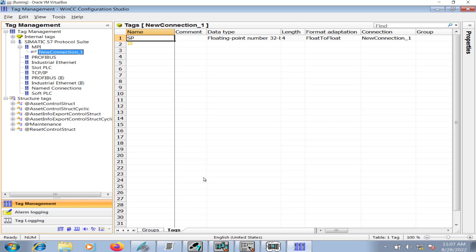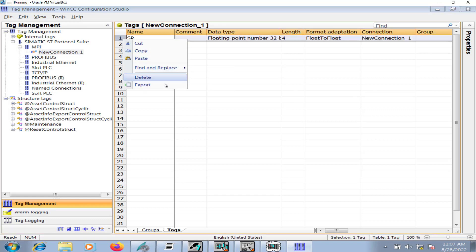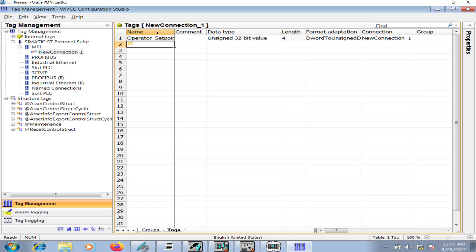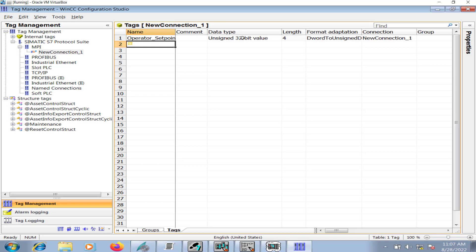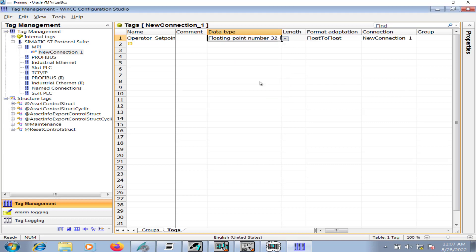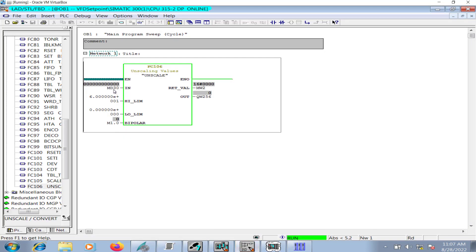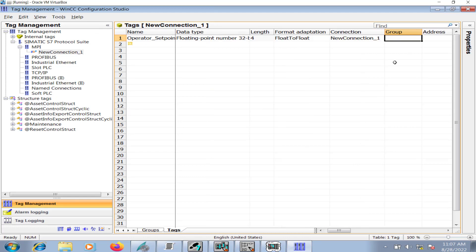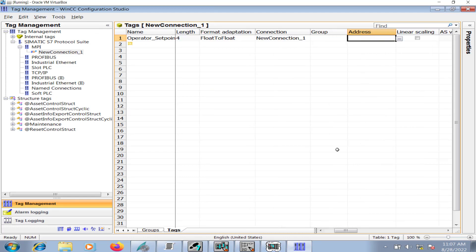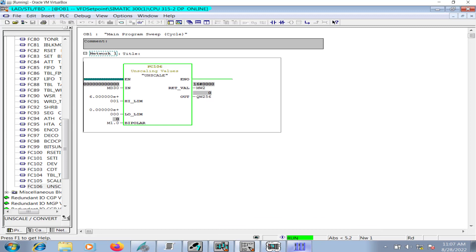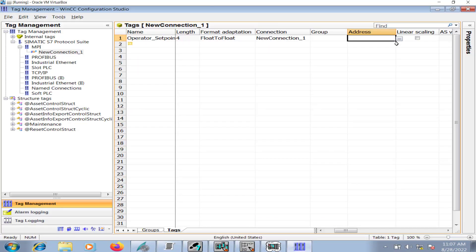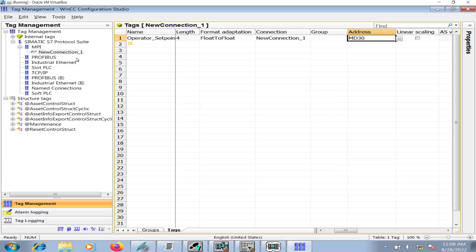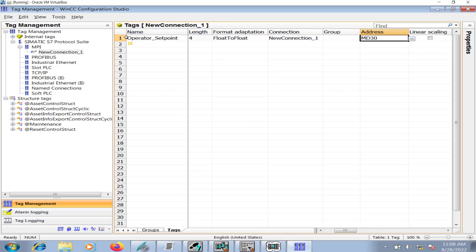Let me enter operator set point. You can give it any name, set point for frequency. The data type is 32-bit floating point, 32-bit because MD 30 is a 32-bit data. The connection, new connection one, this must be the same. For address I go MD 30, so you will give it the address MD 30, bit memory double word 30.